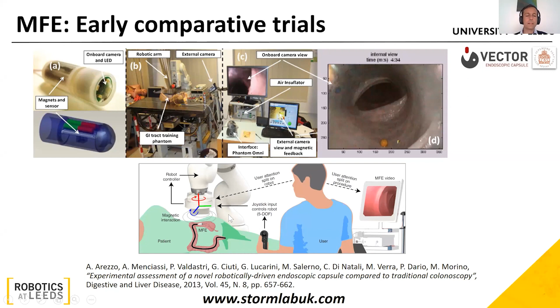However, the robotic procedure was 3 times slower, which is not acceptable from a clinical perspective. The reason for this disappointing result was related to the assumption that the magnetic endoscope was free to move in the insufflated colon, following the motion of the external magnet. This was not always true, as sometimes the tip remained trapped into tissue folds or the tether hampered the motion of the tip in a certain direction.